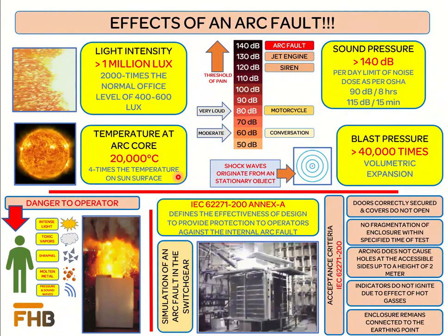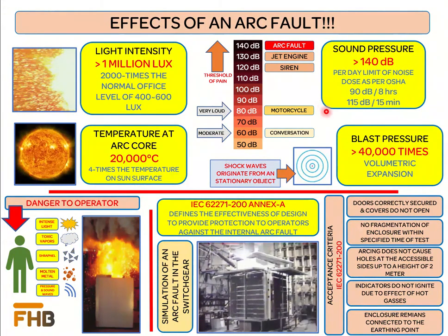The high temperature resulting from an arc fault liquefies and vaporizes the copper, aluminum, and steel parts used in the installation. Since the metal parts change state from solid to vapor, this causes volumetric expansion and results in sound and pressure waves. The sound blast resulting from an arc fault can be as high as 140 decibels and can cause eardrum rupture, resulting in temporary or permanent hearing loss. The high pressure waves can throw operators working nearby across the room against a wall or other installation. The molten metal sprayed and flying metal parts resulting from the explosion can cause severe injuries and equipment damage.